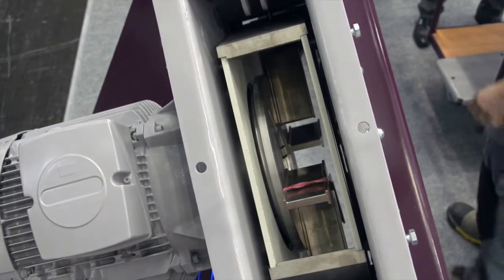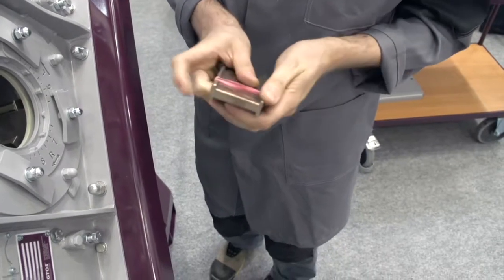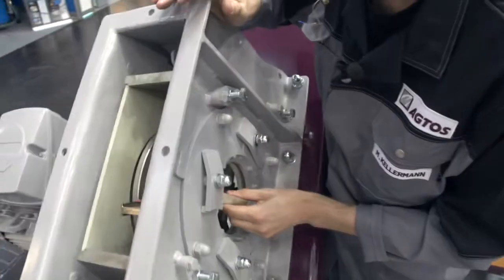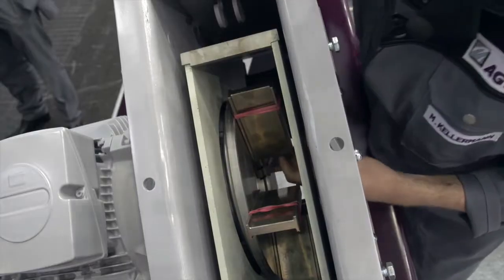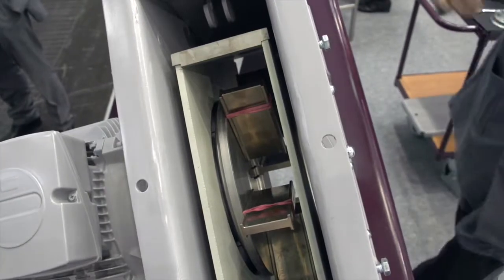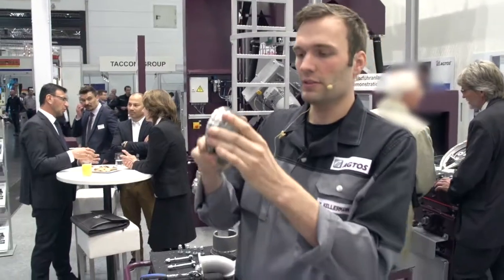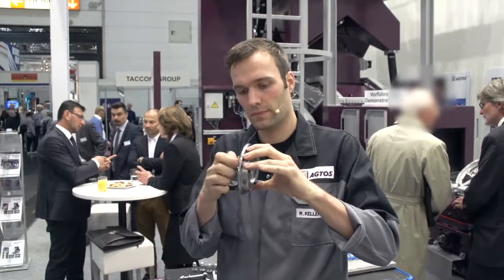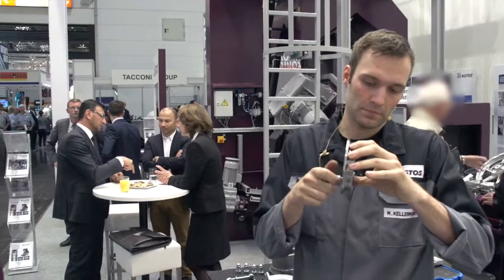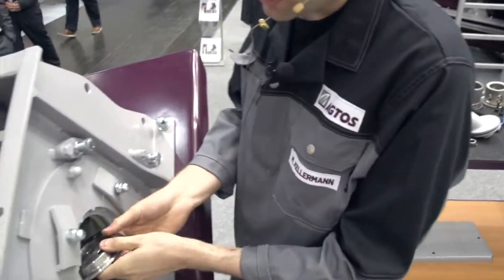The rubber bands remain in the machine. During operation, they will be ejected from the machine via the abrasive circuit. The headless screws must be unscrewed so that they are flush with the surface of the clamping disc. Then reinstall the clamping disc and tighten it in a defined manner by way of the torque spanner.